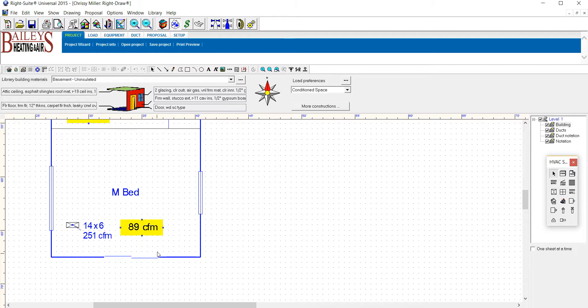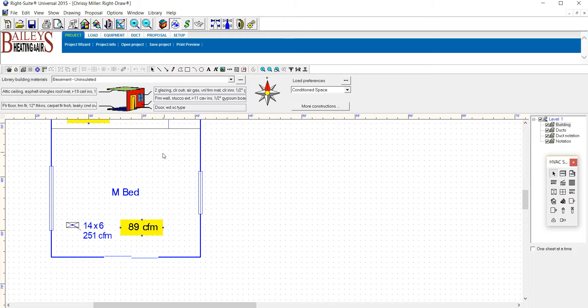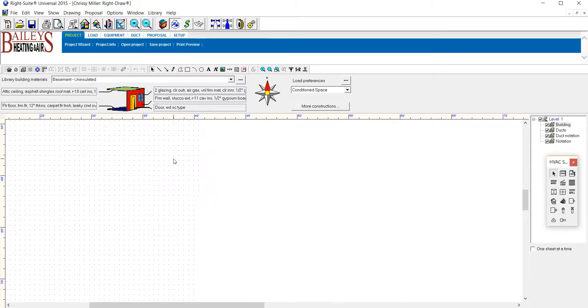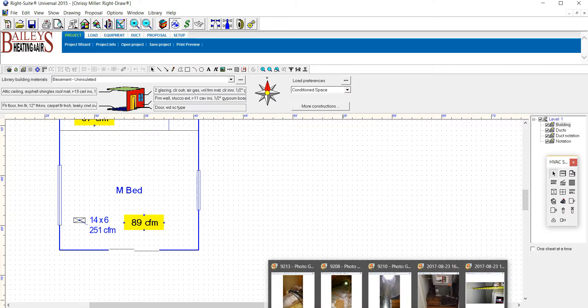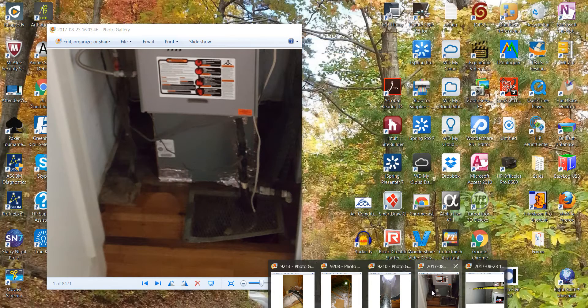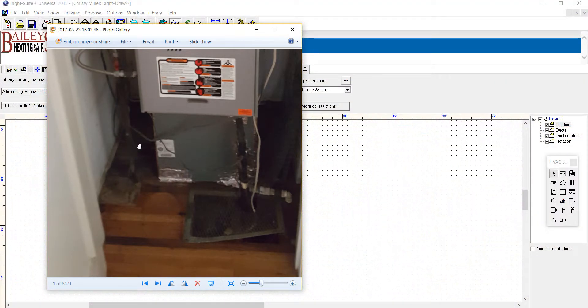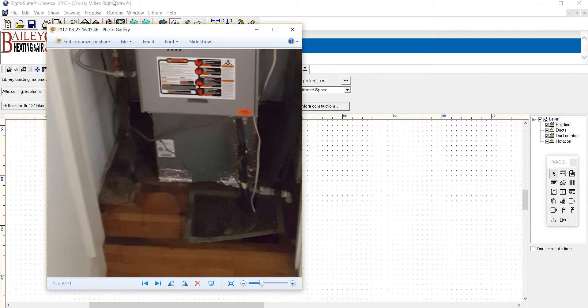That's what we should be getting in the room. This is the reason why they put that mini split in there, and that's a huge issue that needs to be taken care of. There's no way we're gonna run another duct under the house to get there, so what I would suggest we do is put a duct beside the furnace here and run it up alongside the furnace.